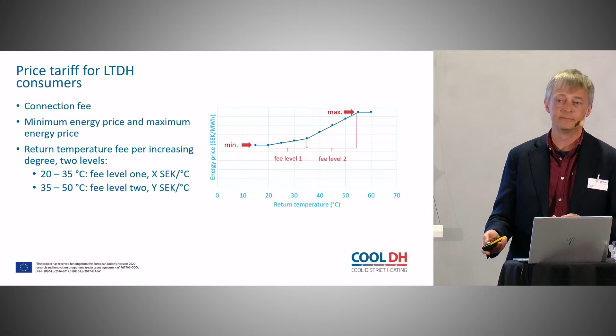This led to one important thing: a close cooperation with those designing the housing systems, which was exactly what we wanted. In the beginning we got a lot of questions - how should I design the heat exchanger, how should I design the heating system inside the building - that was exactly what we wanted. I'm afraid we're right now at around 40 degrees return temperature, which is slightly higher than we wanted and expected, but it would work.